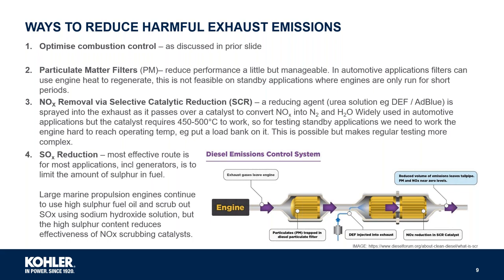We can fit SCR systems to reduce NOx. This is where a urea solution is sprayed into the exhaust, and as it passes over a catalyst, it converts around 95% of the NOx into nitrogen and water. Widely used in automotive applications, but the catalyst needs to reach 450 to 500 degrees C to work. So for testing standby generators, we need to work the engine hard to reach these operating temperatures, which can be done by putting them on load banks, but it makes regular testing more difficult.